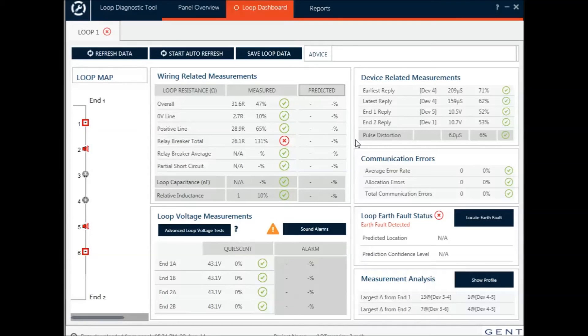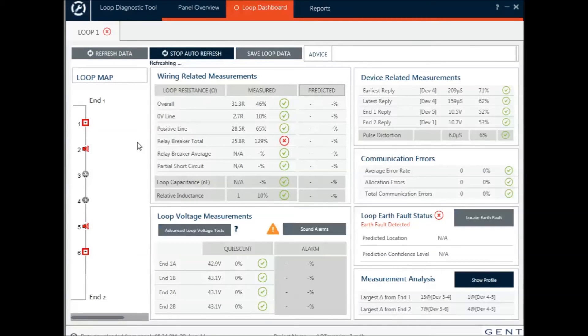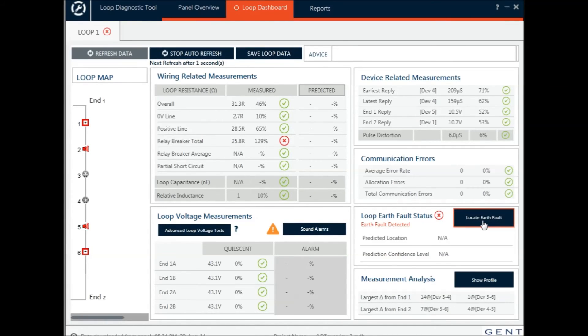When you've gone to resolve the problem, you can reallocate the loop or you can refresh the data. Because I've not actually solved the problem, this is still coming back. You can also ask it to continue the refresh so you get a running update — if you're getting someone to try and solve the problem you can see here when the problem has been solved. However, because I've not done any fault finding, I'm going to try and locate the earth fault.